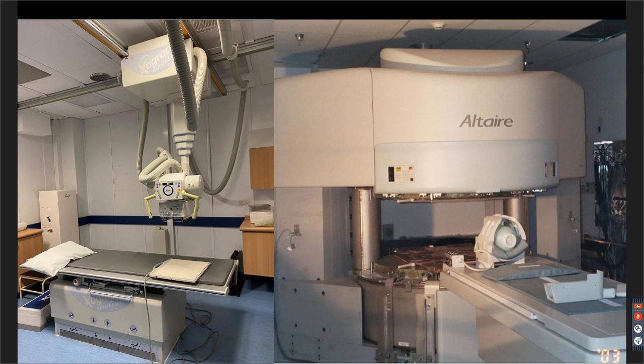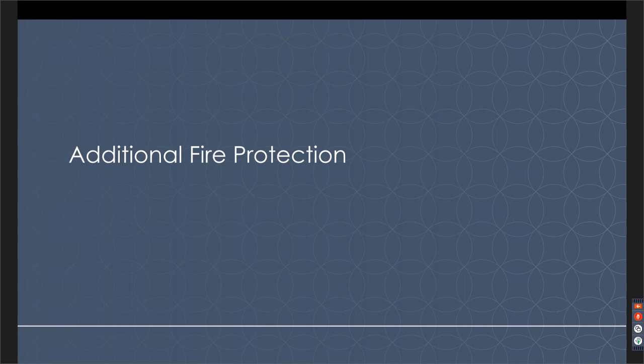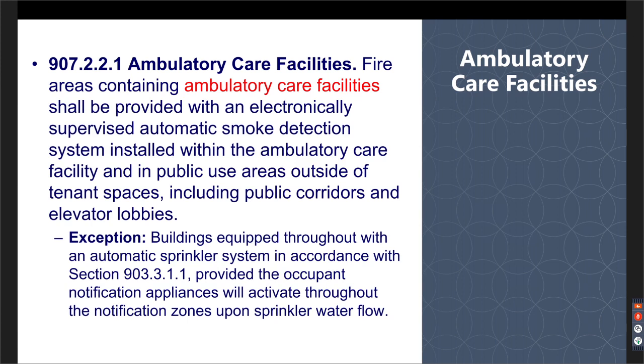And then bringing it around to additional fire protection systems. Most of the time we're talking about fire alarm, but maybe other stuff as well. In 907.2.2.1 for ambulatory care facilities, this section of the code for these B occupancies requires an electronically supervised automatic smoke detection system installed within the ambulatory care facility and in public use areas outside of the tenant space, including corridors. The code says, however, if the building is sprinklered, then an occupant notification will activate throughout the building when the sprinkler system flows, and an automatic smoke detection system is not required.